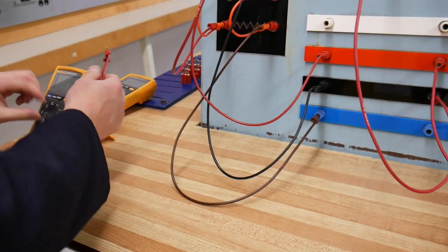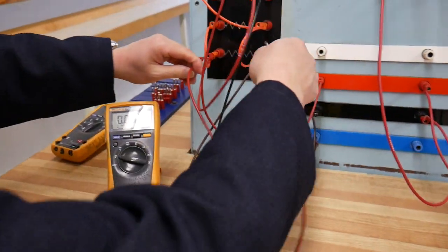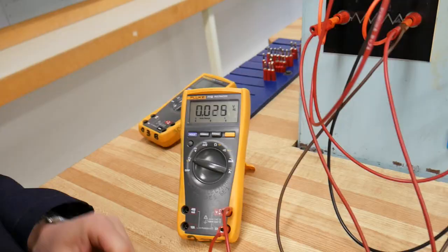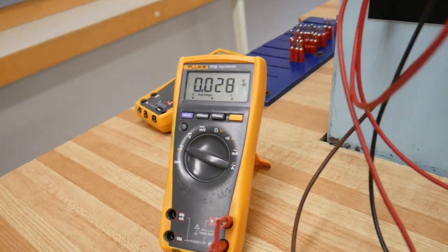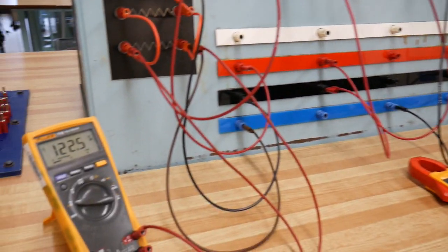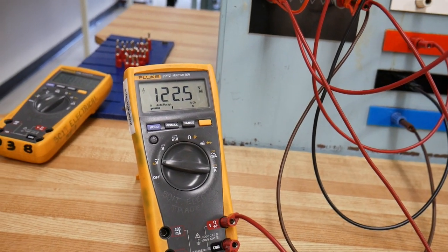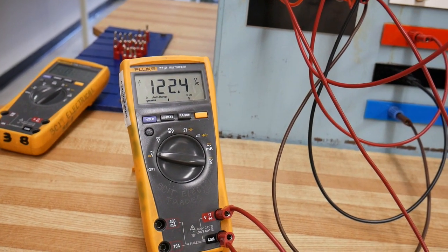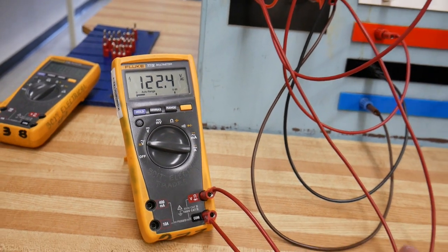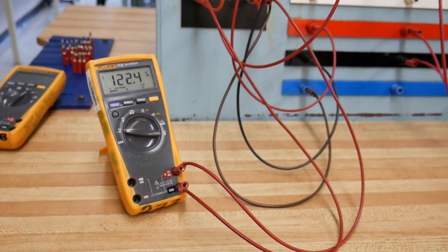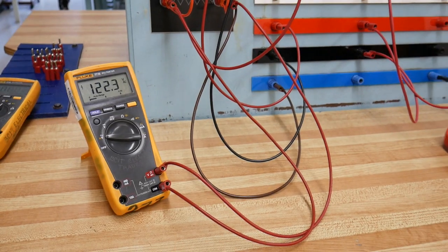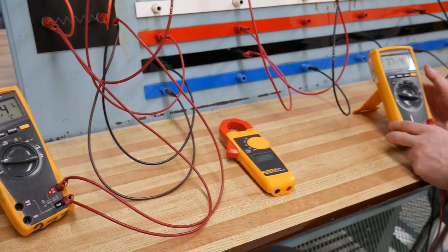I'm going to put this meter in to measure the phase voltage on the load. I'll turn the power on. When the power is on, I did the calculation: secondary phase voltage should be 120 volts. This meter is reading 120 volts for my load phase voltage.